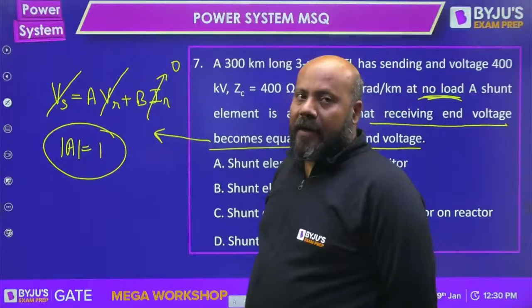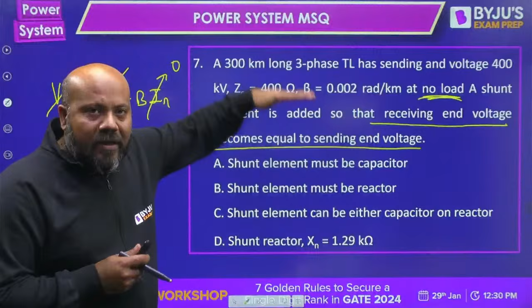Why have I added the reactor? Because in general, at no load condition, the receiving end voltage is more than the sending end voltage. That is the Ferranti effect, and you want to avoid that. To avoid it, you need to reduce the no load receiving end voltage, and for that purpose you connect the reactor.